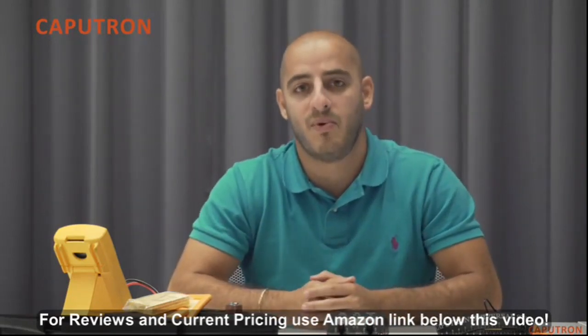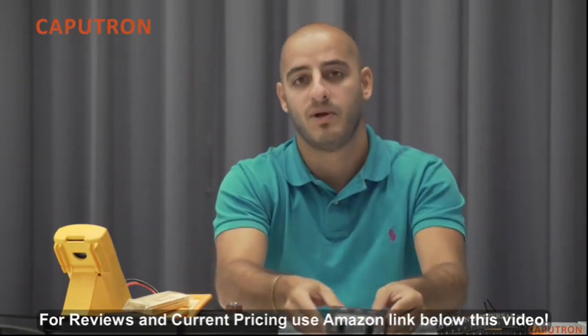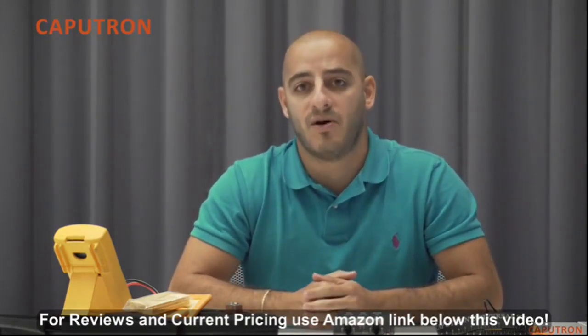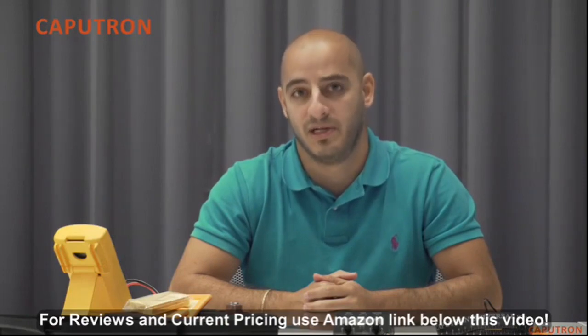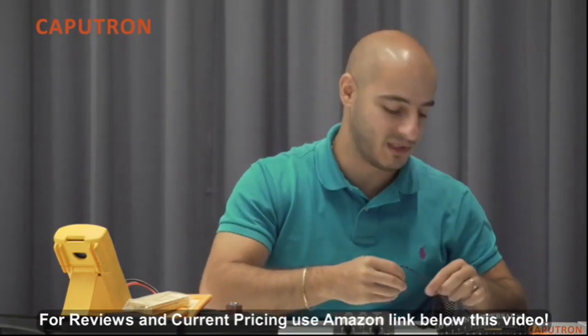When you have chosen the current, you rotate the knob to start stimulation. You will notice at this point the device is beeping and the screen displays electrode reject. What this means is that the electrodes are not connected, or if the electrodes are connected, you do not have optimal contact quality and should adjust the electrode positioning. Remember, you will also need to use saline solution and we recommend 0.9%.